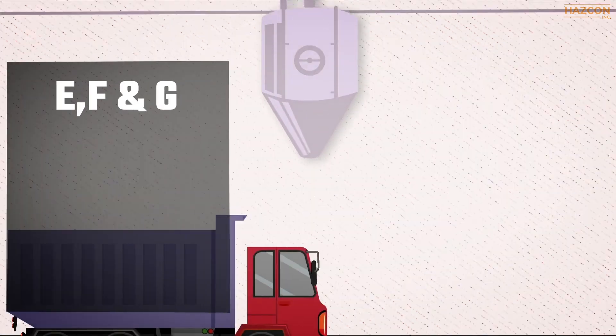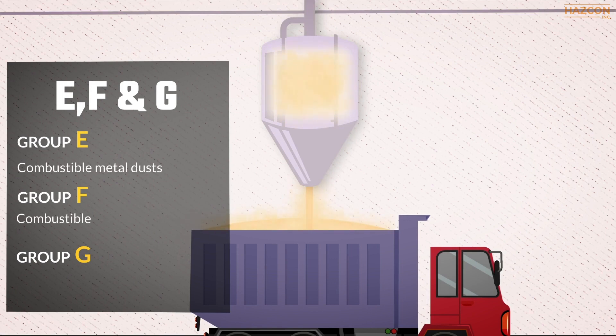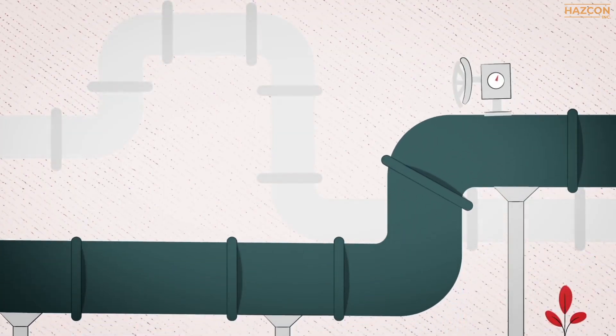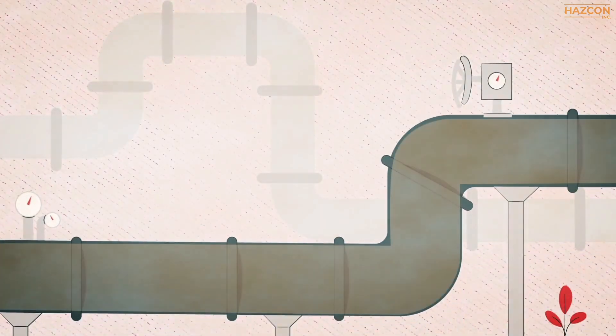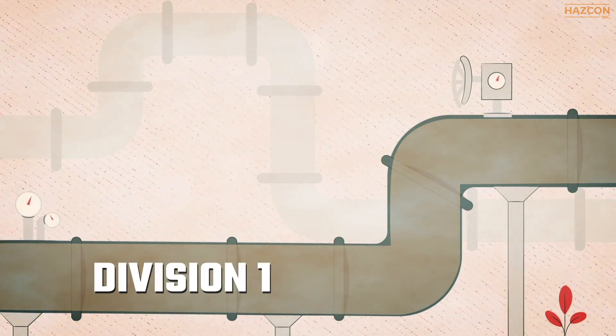The three dust groups E, F, and G in North America further define dusts as follows: Group E — combustible metal dust; Group F — combustible dusts that are not metal; and Group G — solid particles including fibers. If there is conductive metal dust in the area, for example, then the entire area where the dust may collect is considered to be Division 1.